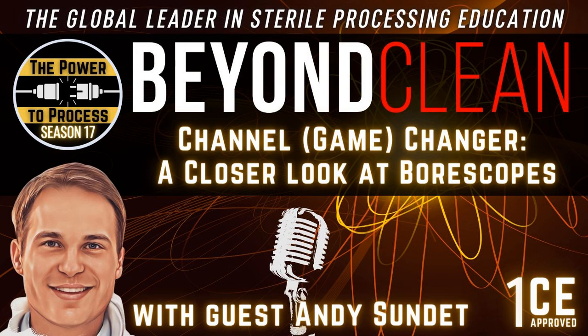It's very small. These borescopes don't have a working channel themselves, so the leak testing and some of the preventive maintenance that you do with other endoscopes isn't really relevant. But the typical stuff that we do is visually inspecting the borescope to make sure that there's no visible damage, kinks, breaks, or tears in the flexible portion of the scope. You're inspecting the tip to make sure that there are no burrs or sharp spots on it. A lot of those things you would already have been trained to do with regular flexible scopes, whether small diameter OR scopes or larger diameter scopes used in the GI, there are commonalities in what you're inspecting for, especially that distal tip, and making sure that you don't bang it off of something.